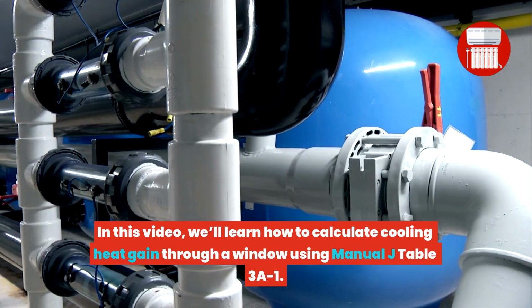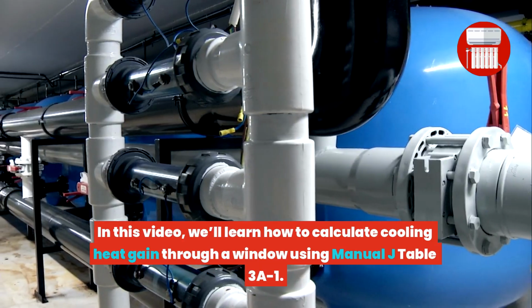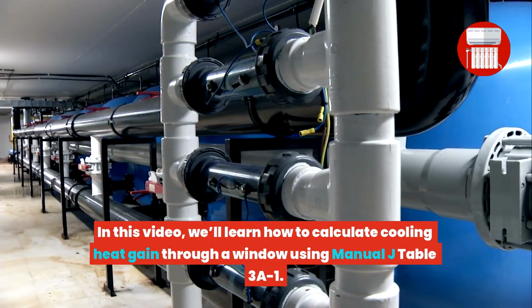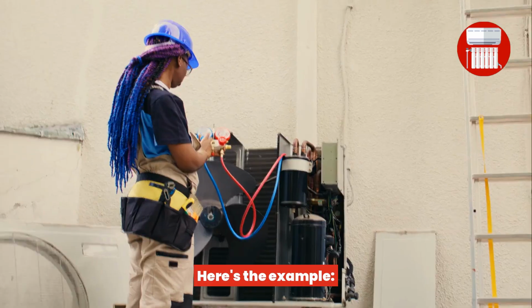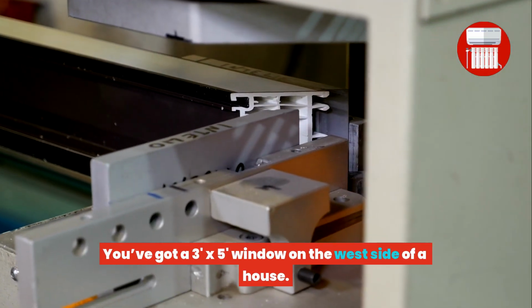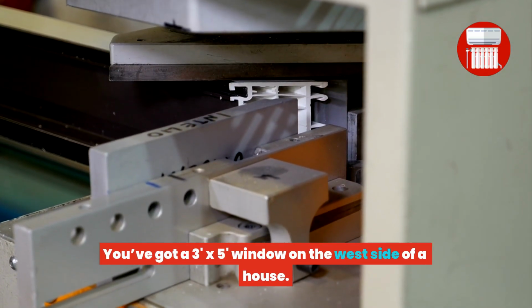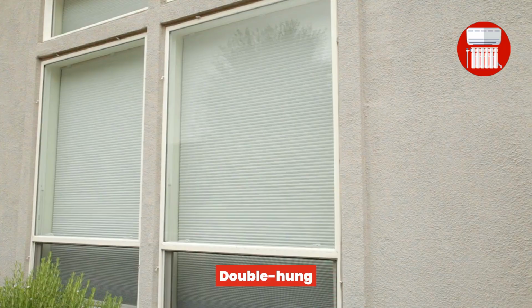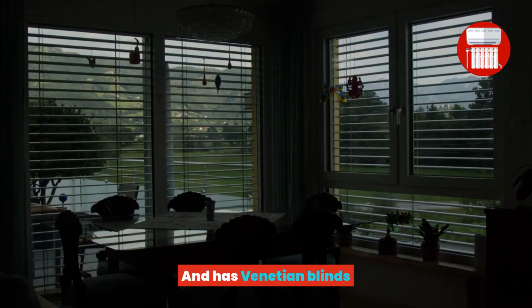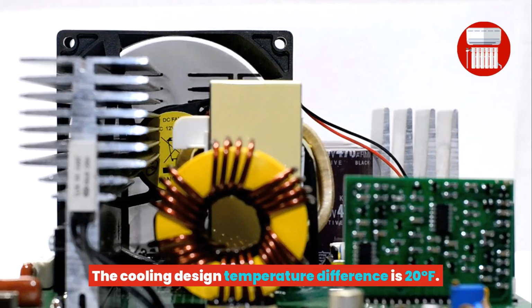In this video, we'll learn how to calculate cooling heat gain through a window using Manual J Table 3A-1. Here's the example. You've got a 3x5 window on the west side of a house. It's clear double-pane, double-hung metal with no thermal break and has Venetian blinds. The cooling design temperature difference is 20 degrees Fahrenheit.